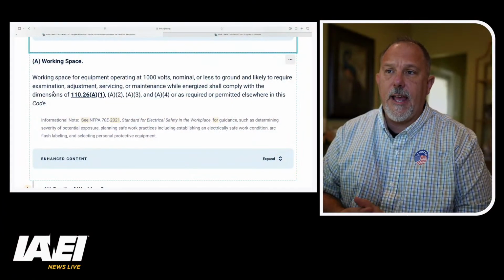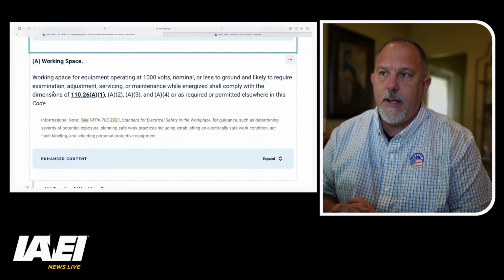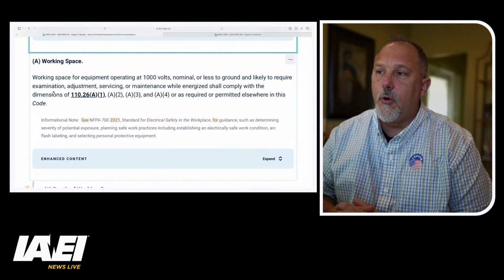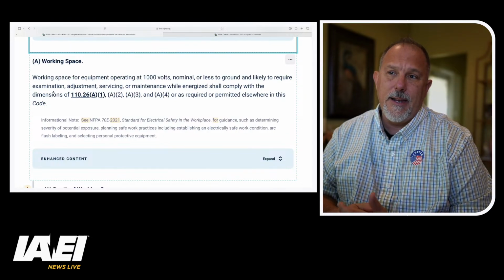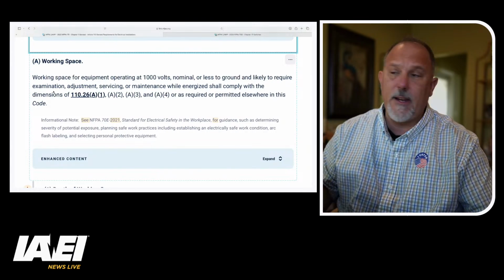And the point of discussion, Felix and Steve, for anybody else who's come to the table a little bit late, Willie Snyder said a good example of a product is one not likely to be worked on energized or maintained. The way the language reads in working space, it says, or less to ground, and likely to require examination, adjustment, servicing, or maintenance. So we're looking at examination. Would I have to examine it in an energized state, make any adjustments, or do any servicing while energized, or maintenance? I know maintenance is something I can wrap my head around, and we have a document associated with it.